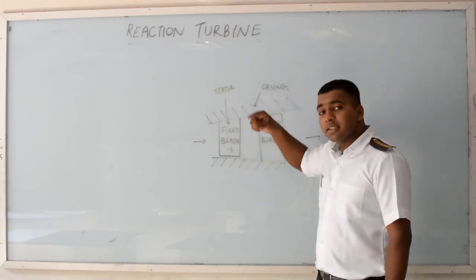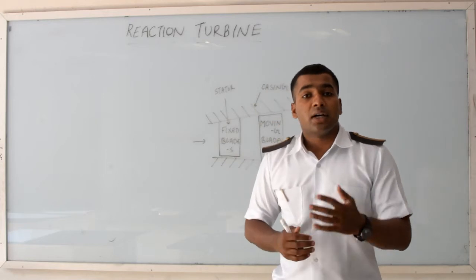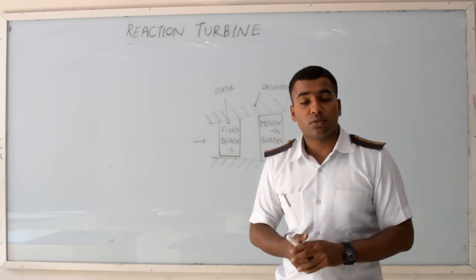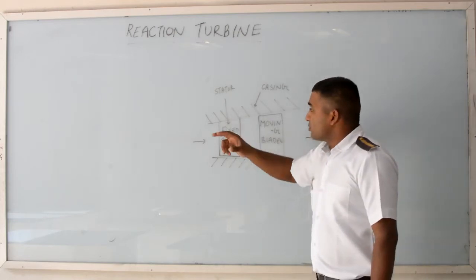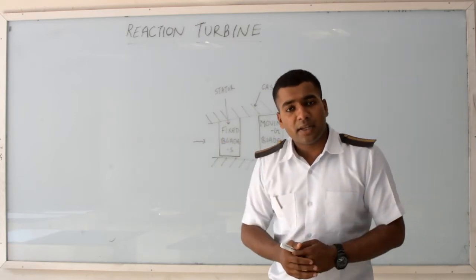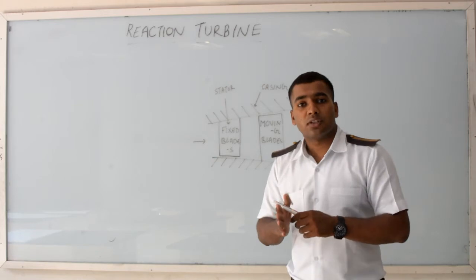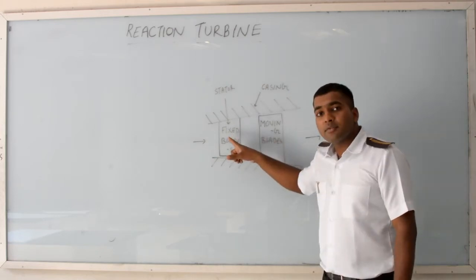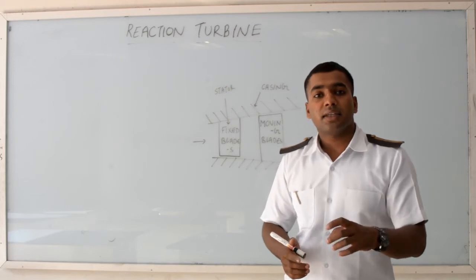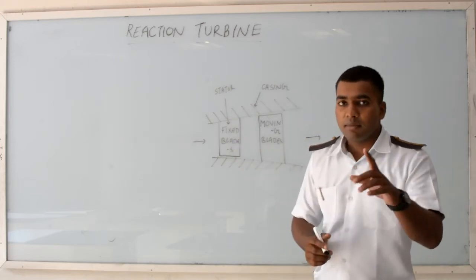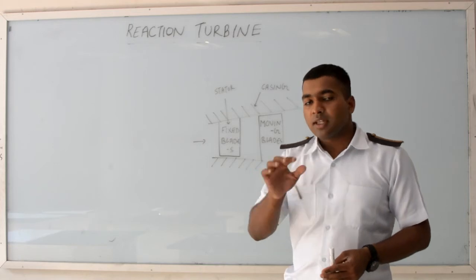The increase in velocity of the steam will impact on the moving blade. Now you must be thinking that these fixed blades are nozzles fitted on the Reaction Turbine, but that is not so. In a Reaction Turbine, conventional nozzles are not fitted. The passage provided for the stationary blades is designed such that they act as nozzles — the passage increases the velocity of the steam. That is why we say the stationary blades are acting as nozzles, but actually there are no nozzles fitted in a Reaction Turbine.